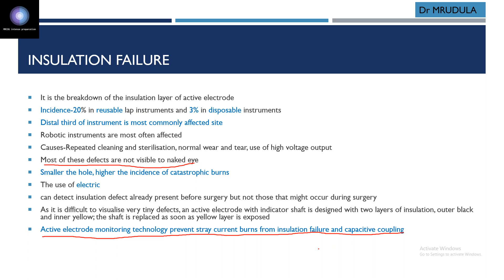Active electrode monitoring technology prevents stray current burns from insulation failure and capacitive coupling. So this is again one question. What is active electrode monitoring useful for? It is only useful for insulation failure and capacitive coupling. It is not useful for direct coupling. Okay.